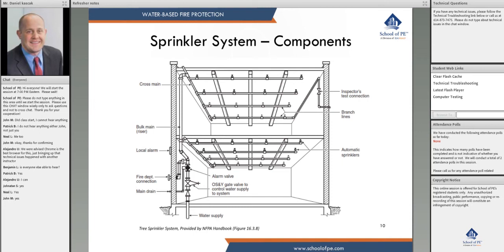Cross mains are mains attached directly to branch lines. Branch lines are piping with sprinklers — you can see sprinklers at the ceiling connecting to a branch line, which ties into a cross main, which ties into a feed main. We also put an inspector test connection in so we can test the flow of water and the alarms.